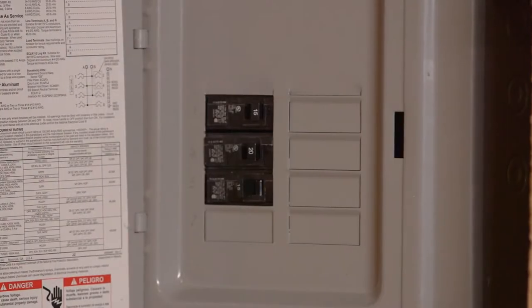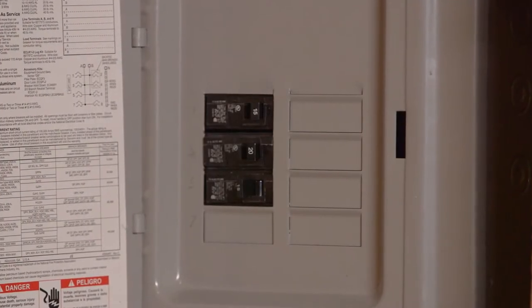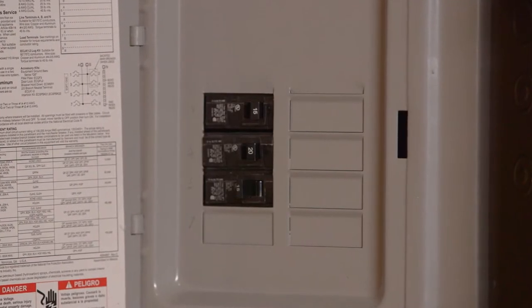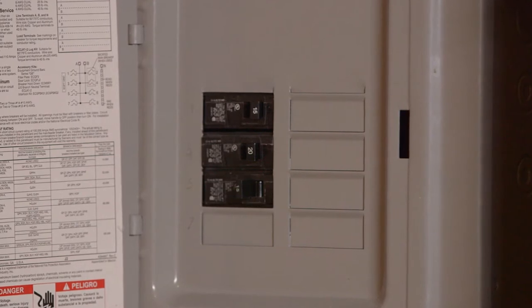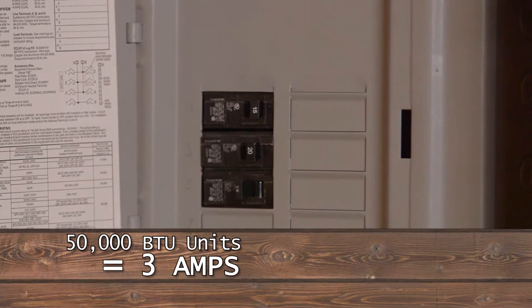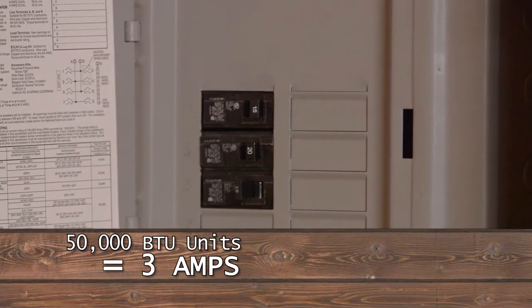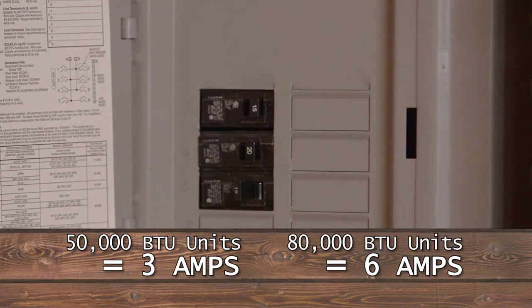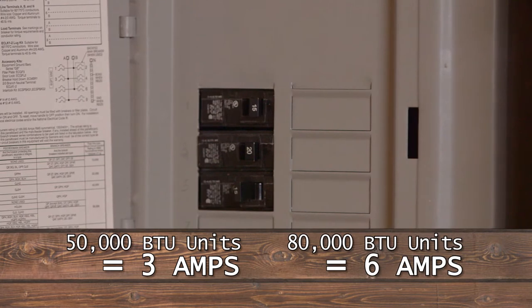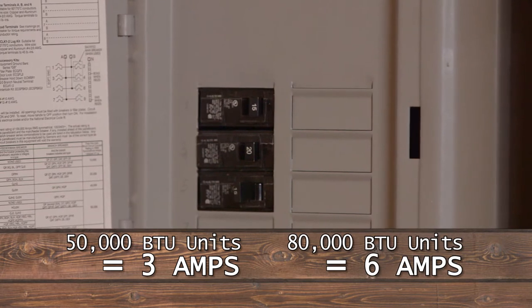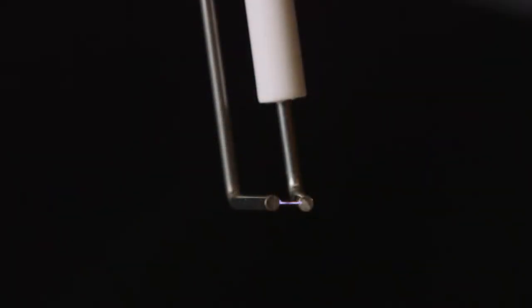Remember, electrical connections require a minimum of 15-amp service. 50,000 BTU units draw 3 amps, while 80,000 BTU units draw 6 amps. This unit uses a direct spark ignition system. No pilot is necessary, since the spark lights the main burner when the gas valve is turned on.